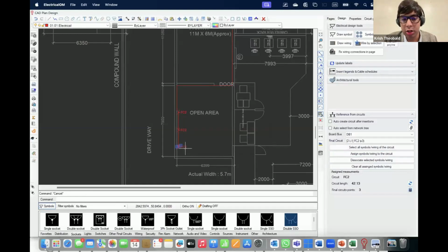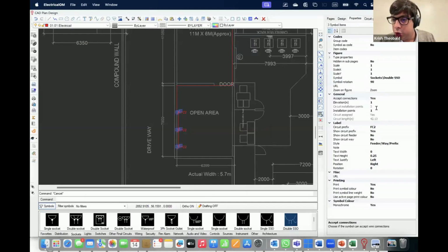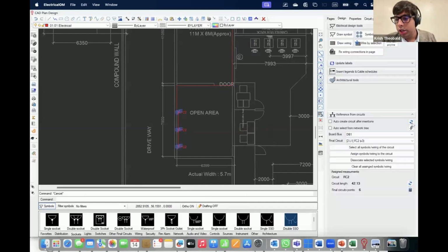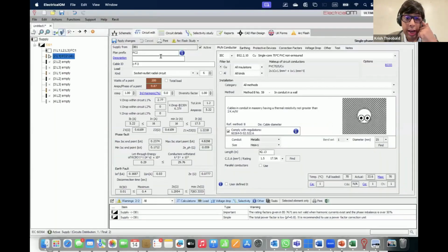So if I do select similar properties and I change this to installation points 2, now it's automatically 6. And if I apply, that goes there. Now, if I shut the CAD plan add-on and I go to my circuit edit, you can see I've got 6 into 200 watts and 42.13 meters.